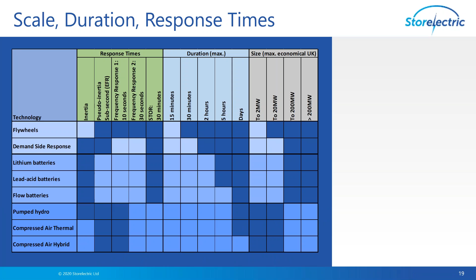So, in conclusion, the question is, which is the winning technology? And frankly, every single technology needs something, has its place in the system. You can see here, I've put a correlation between response times, durations, and size for the various different technologies. And you can see that they all have different profiles, which is why they can all have something to contribute to the system. The problem we've got at the moment is that people are expecting certain technologies to do everything, especially batteries. They think the batteries are the answer to all prayers, but they're not suitable for every single technology. They can't deliver real inertia. They can't deliver long durations cost effectively or immense scales. So therefore, we need a really good mix with all of these technologies, and all together enable renewables to power the grid.